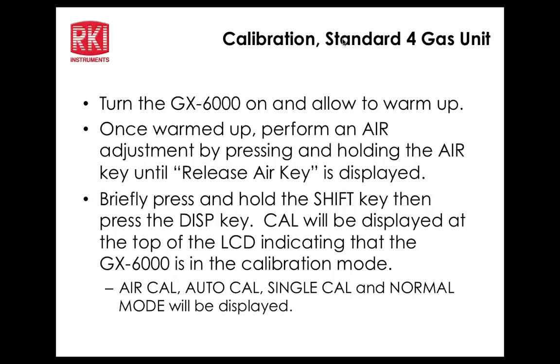Okay, now it's calibrated to 100. Okay, now we are done. Disconnect the gas. We're back to the sub menu of the calibration menu. And I just want to simply go to escape now. Ordinarily, if you don't want to hear the alarms, just go ahead and let it run like this with the alarms deactivated. But if you go quickly to escape, you'll probably get some alarms, likely.